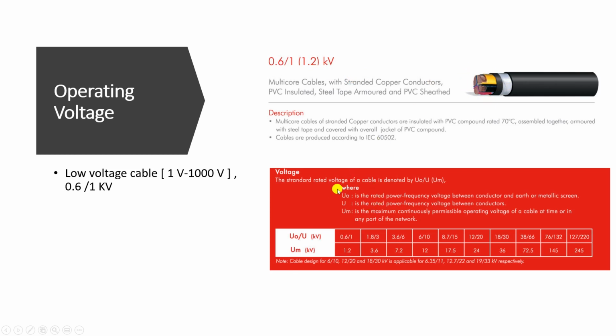As you can see here, these are the definitions: U0, and U which is 1, and 1.2 which is Um. This is what appears beside the cable inside a catalog. The first one, U0, is the rated power frequency voltage, the voltage between a conductor or a phase and earth, or a metallic screen which is connected to the ground. The second term is the line to line voltage, the voltage between conductors. The third, Um, is the maximum continuously permissible operating voltage of a cable at any time or in any part of the network. This is the maximum voltage which our cable can withstand. Here are also examples of different voltages and different maximum voltages, some standard values.